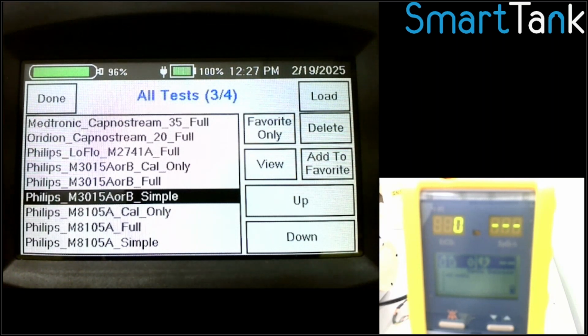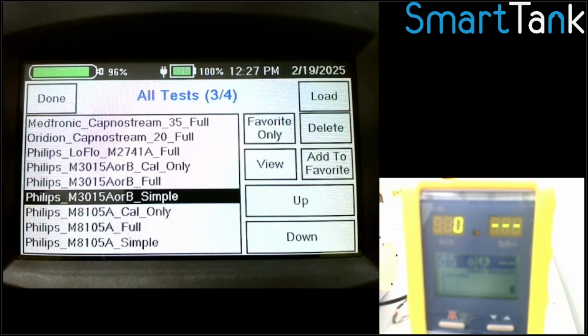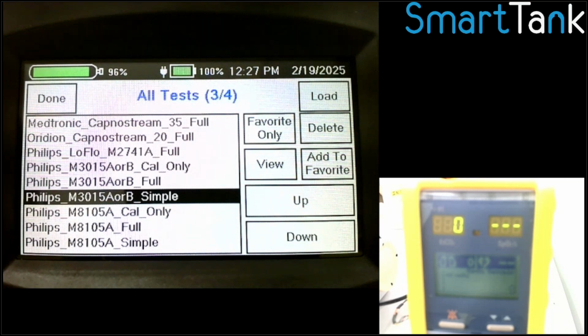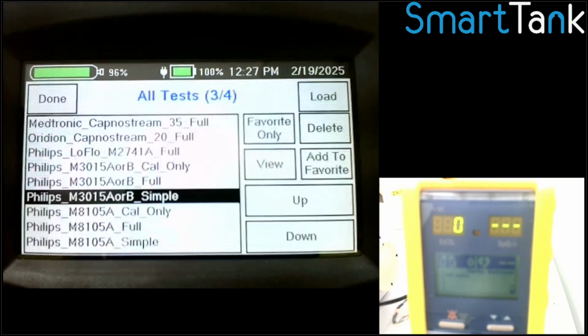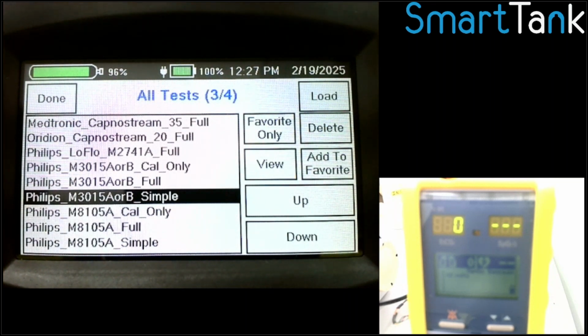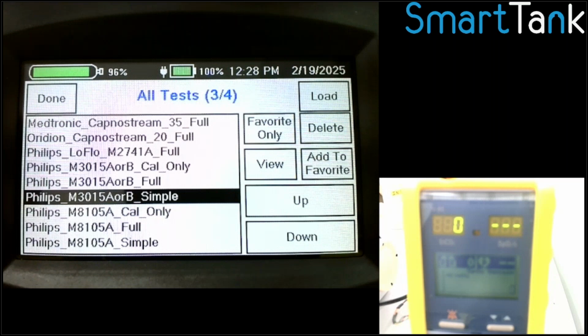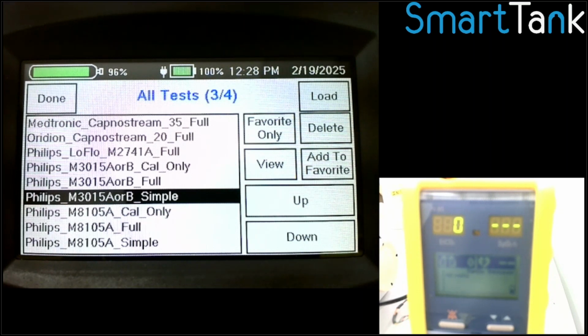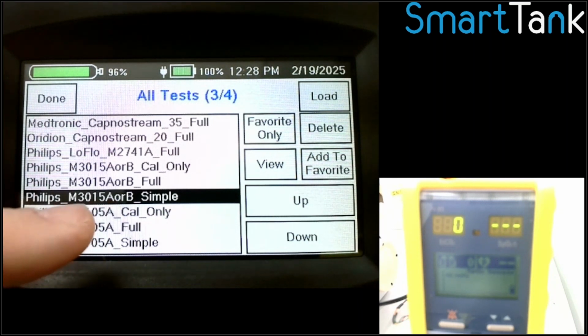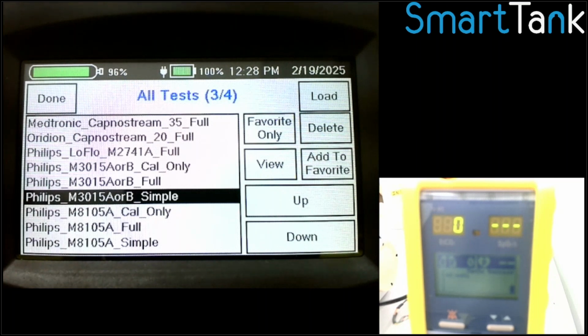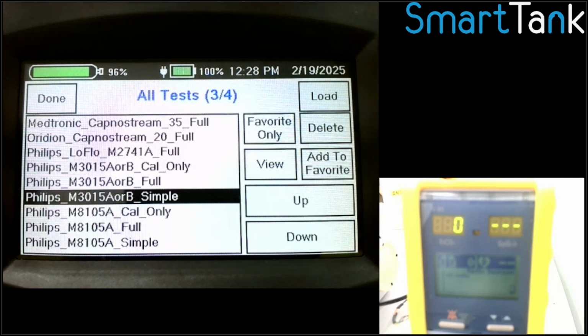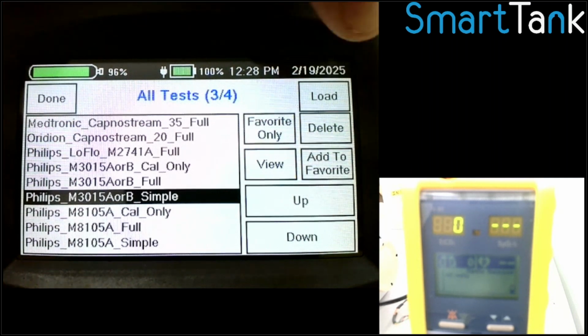In the same manner, if there's a sequence on here, let's say you love the 3015A full sequence, but you want to take 2 steps out or add 3 steps, we will modify those test sequences for free for life. So there's never a charge for that. It's as simple as telling us what you want. We'll create the sequence, email it to you, and you drop it on the SmartTank through the USB, and it will show up here or replace the one that's on there, and away you go. So today, for this demo, I picked this 3015A, simple one. It's the simplest sequence we possibly have. There's only 3 test steps. And so for a demo, it shows you kind of what the SmartTank can do, but it gives you an example. So once I pick that, I'm gonna hit load.